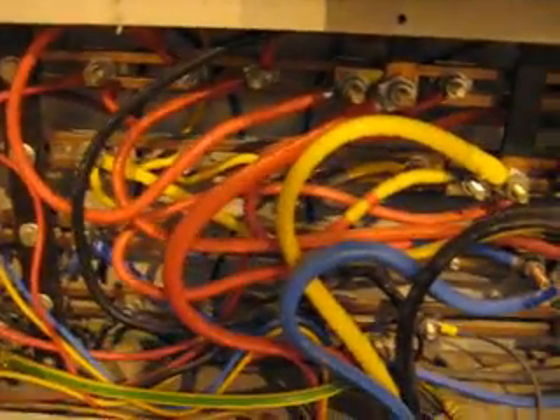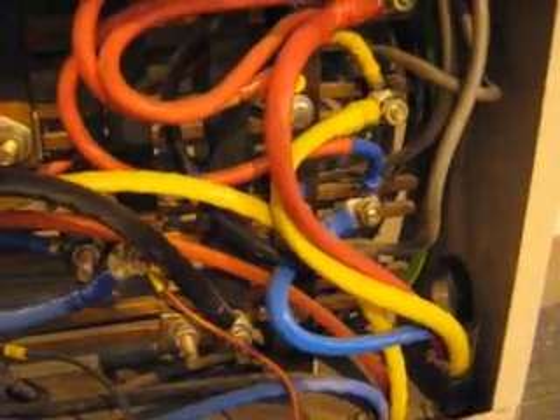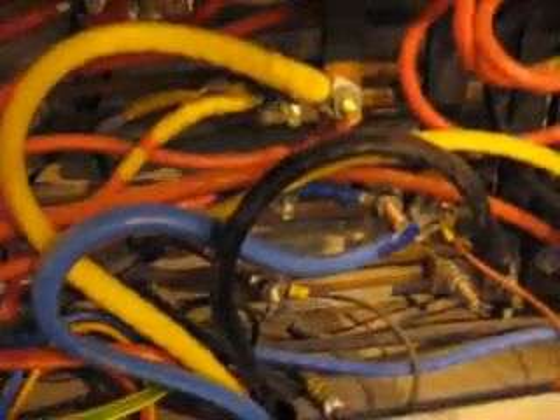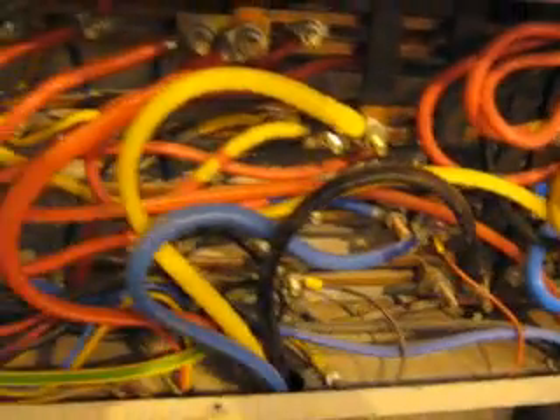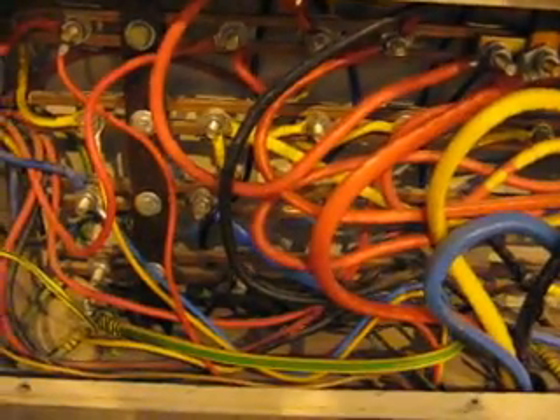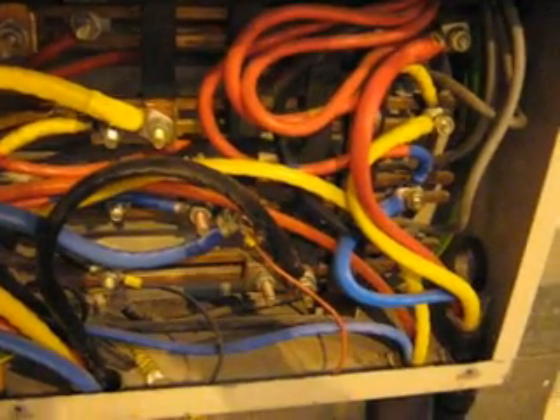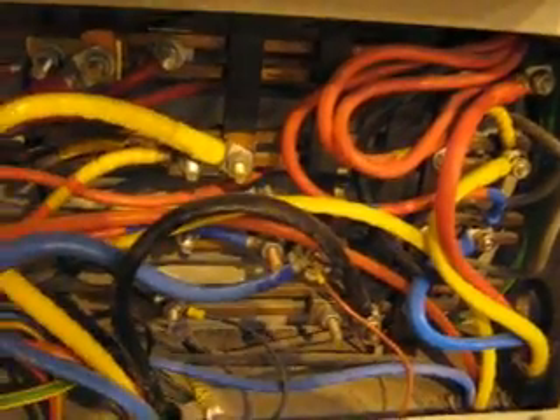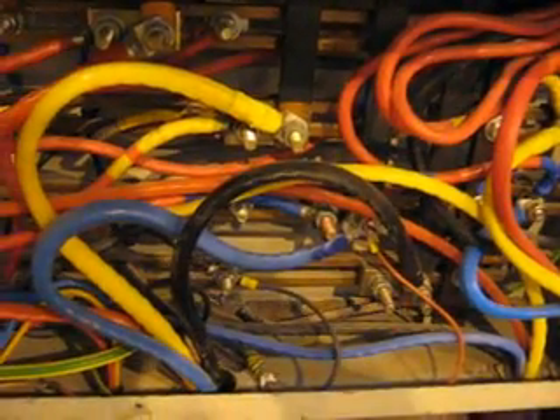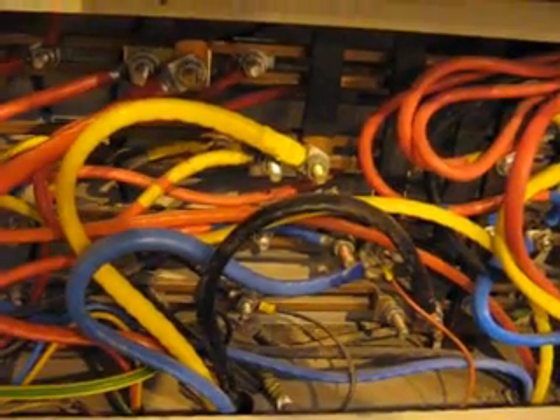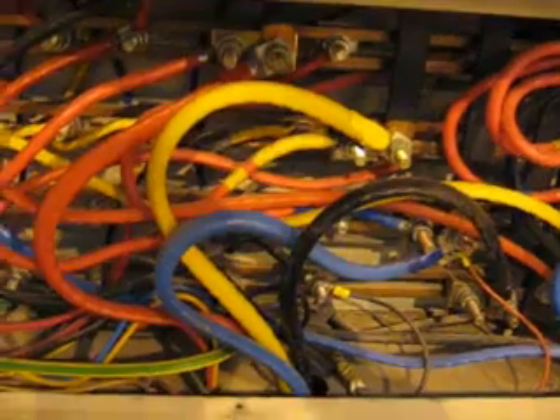Interior of the busbar chamber, which is live and heavily used. These cables here feed the fuse switch we were just looking at, the load side of which is simply sawn off, armoured cable sawn off and just left lying around. So those fuses have got to come out of that fuse switch. To switch it on would be extremely dangerous, and there's no indication by notice or by locking off that you mustn't do that.